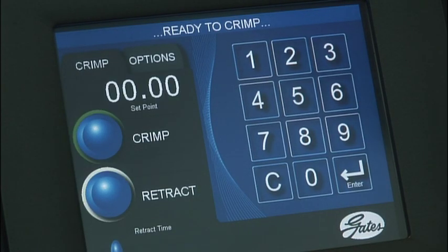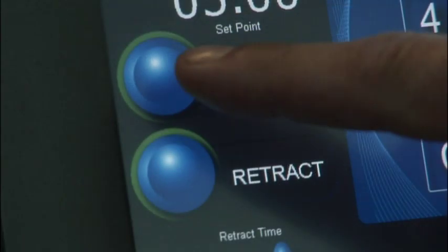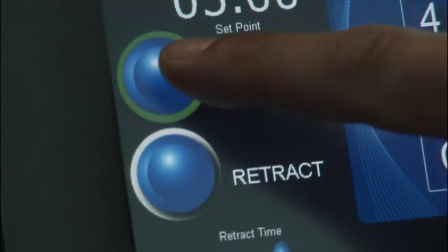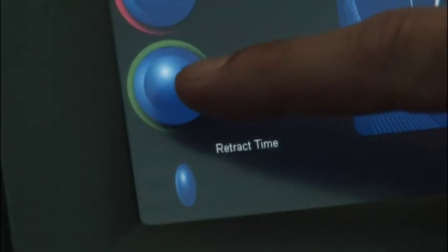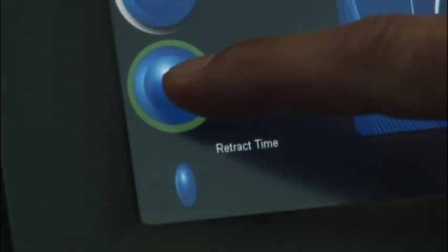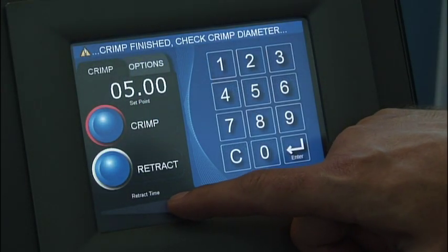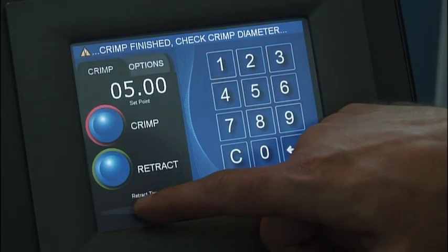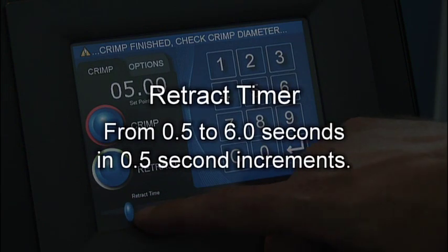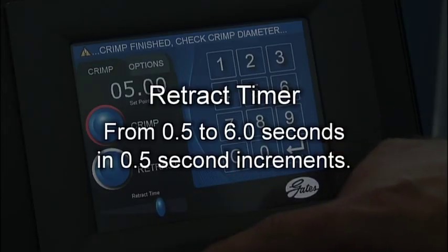The crimp screen, the crimp button. Pressing the crimp button will cause the crimp dies to close. This is a dead man control feature. The retract button. Pressing the retract button will cause the dies to open. This is also a dead man control feature. The retract timer. This slider is a visual indicator for the retract time and can be adjusted between 0.5 to 6 seconds in 0.5 second increments. This is achieved by pressing and sliding the button located at the bottom of the screen, left or right.